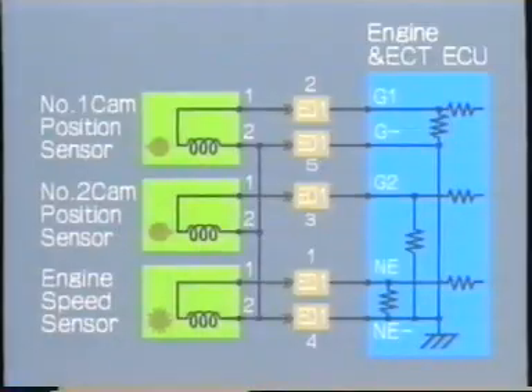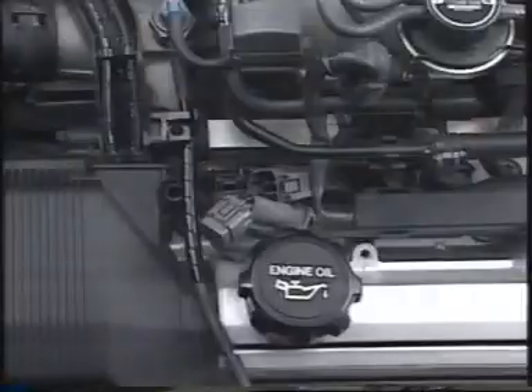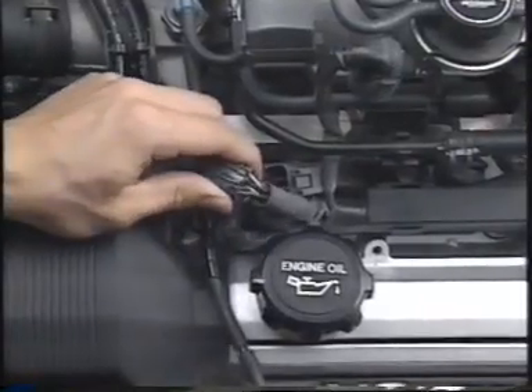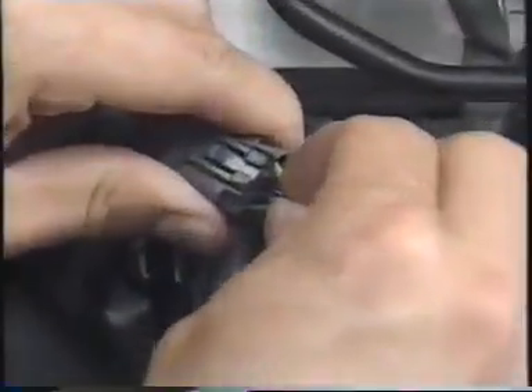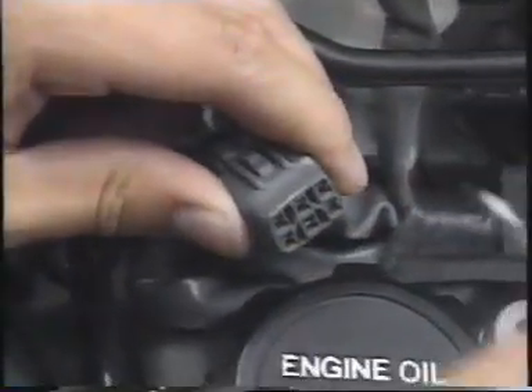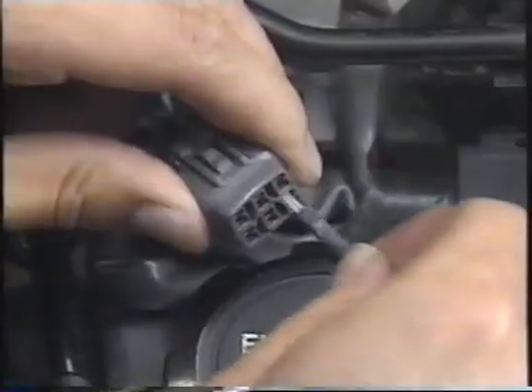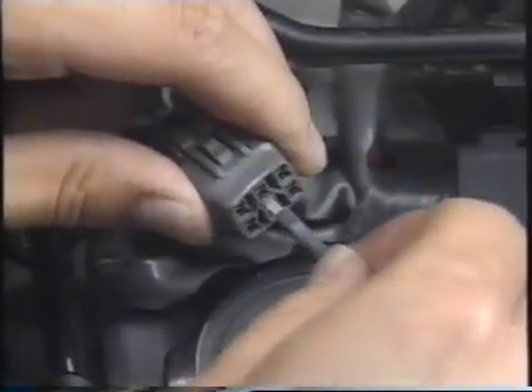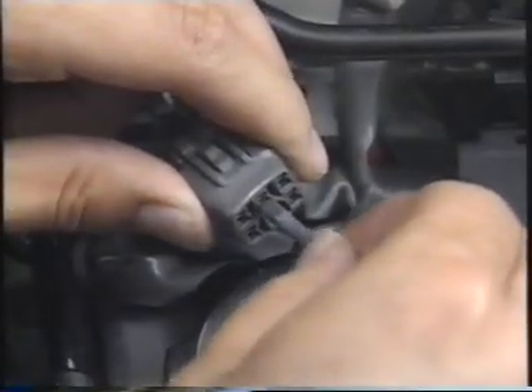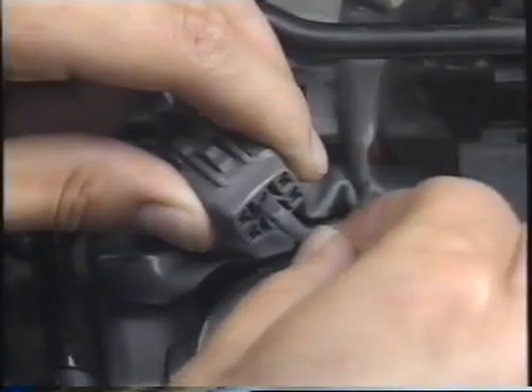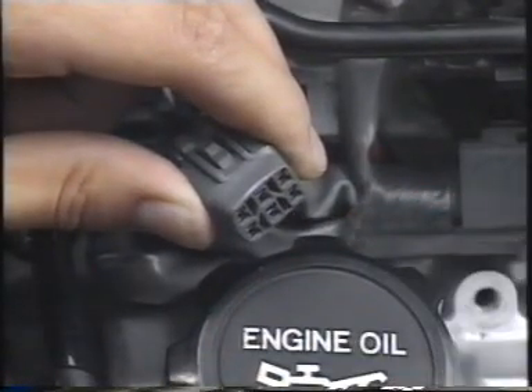So where's the cause of the malfunction? There are still some places left to check. That's right, the ED1 connector. First, is the terminal securely inserted into the connector? They seem to be okay. Next, let's check if it is a good connection. Aha! Terminal 2 is loose. This seems to be the cause of the problem.